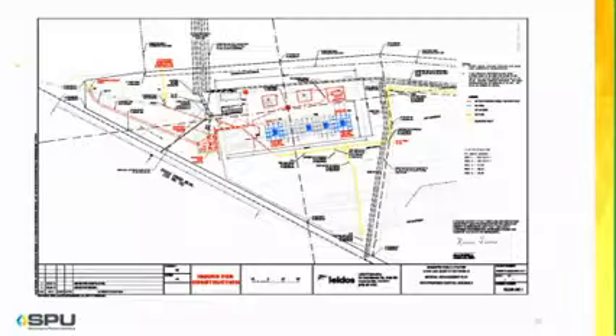The generation comes from the Shakopee Energy Park and runs into the sub onto the 15 kV bus. There's an elaborate system of switching inside and outside the switchgear that enables a couple of the generators at the plant to be tied to one switchgear building, a couple others to be tied to another of the three, and the last of the five generators tied to the third one. It provides a great deal of reliability and the ability for any excess generation to go up onto the grid should that be called for, but we use most everything they generate when they are generating locally.